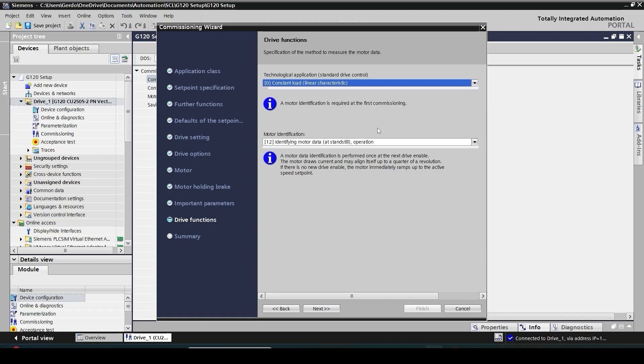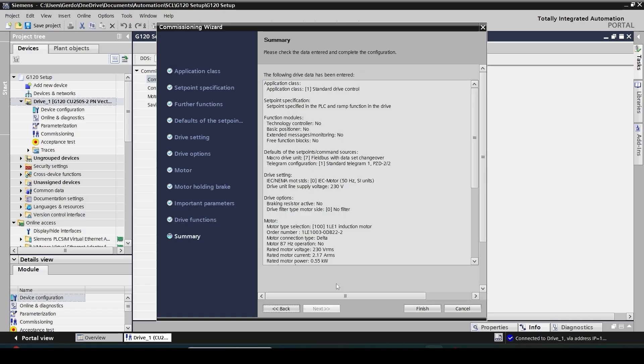What kind of drive function am I going to use? I'm just going to go with the default, constant load. And then also motor identification. During the first time you power up your drive and motor, drive is going to inject some current into motor windings to identify the resistance and other parameters it requires. So I leave it as default, identifying motor data on operation. Next.